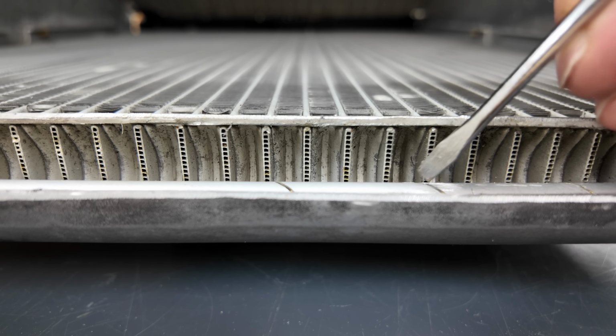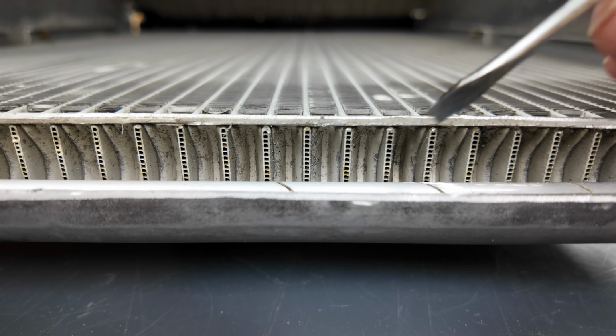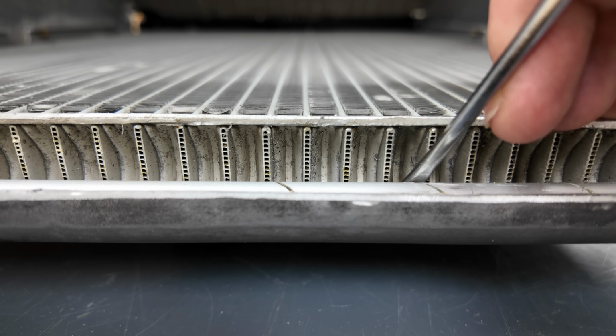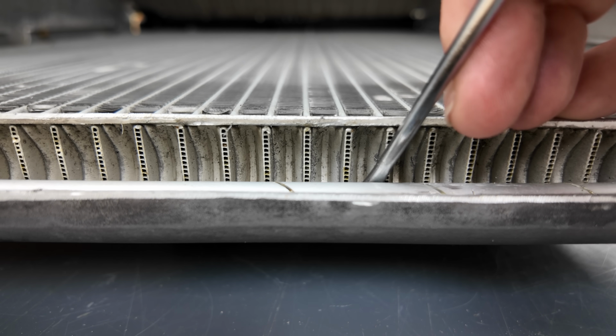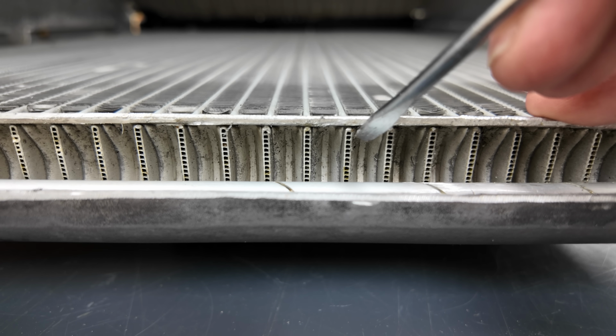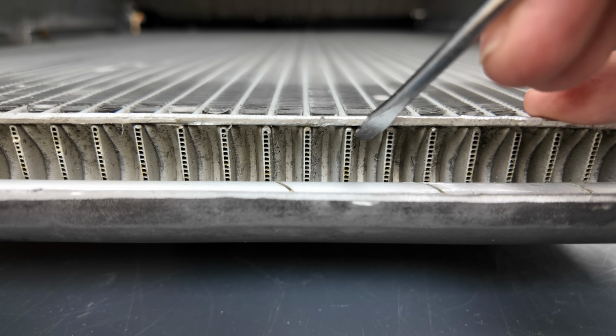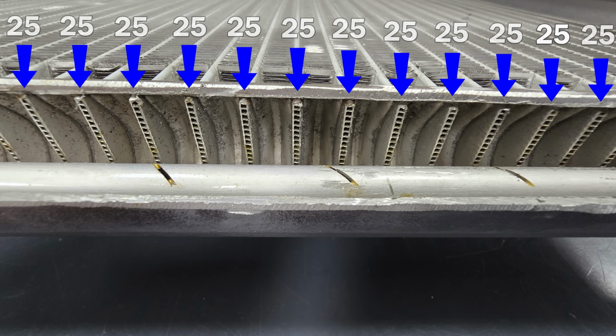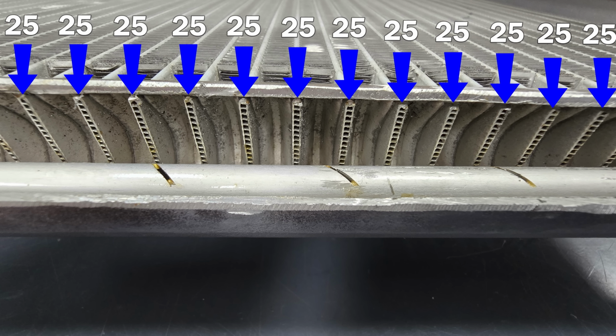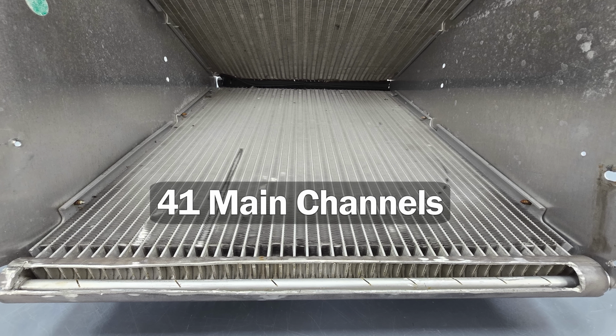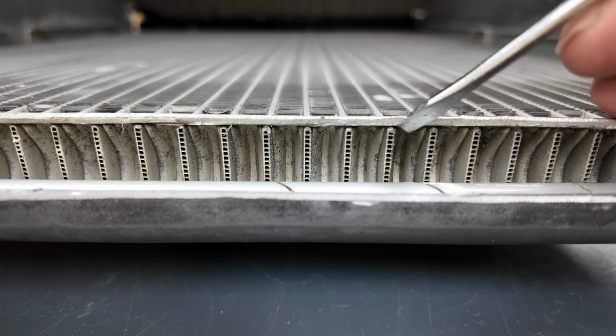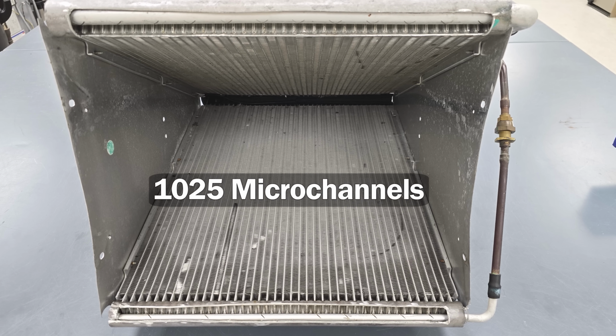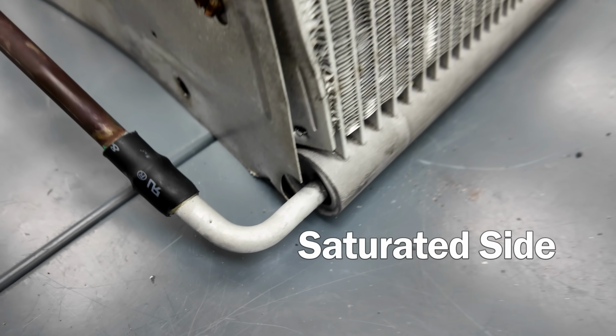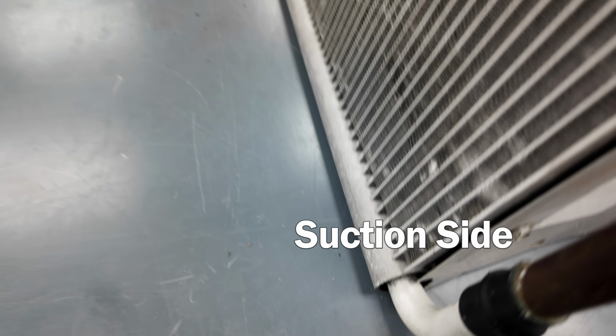After the refrigerant exits through this little slit and gathers into the main header, it's going to enter into these main channels. These main channels are about 1 inch long, and you're going to have about 20 to 30 little microchannels. This one has 25 little tiny pathways for the refrigerant to travel through. And this one has 41 main channels. So we take 41 times 25 and we have 1,025 little pathways for the refrigerant to travel through from the saturated side all the way up in one main channel over to the suction side of this coil.